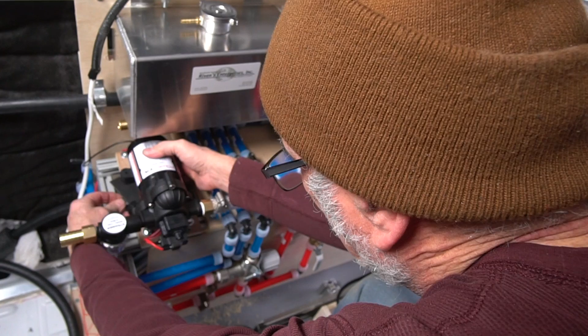So now the water gets pumped down through here. This is fresh cold water from your tank. It goes back into a 3/4 inch manifold, which has 4 zones, 4 half-inch legs coming off of it. Each one of these zones is fitted with a shutoff. Any or all of them can be shut off at any time. And the way I've installed these is the valves are in line with the flow of the water. That is how you would see every single valve in this system. The handle is going in the direction of the flow.